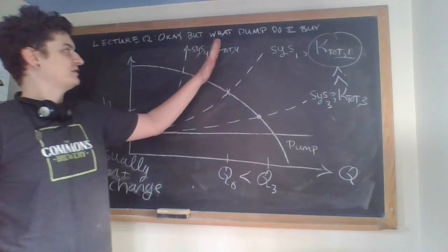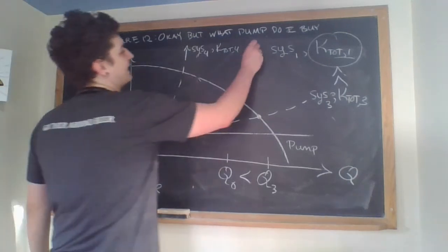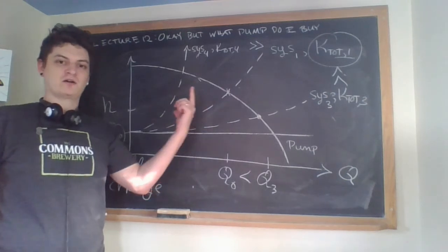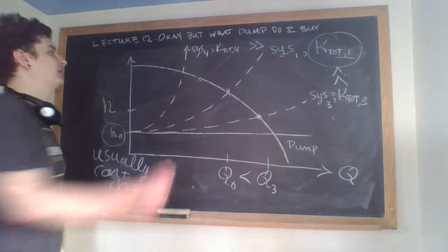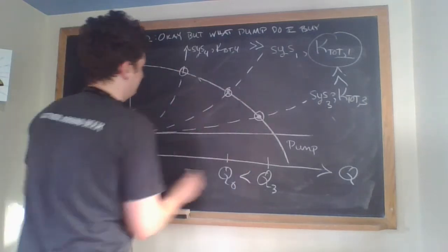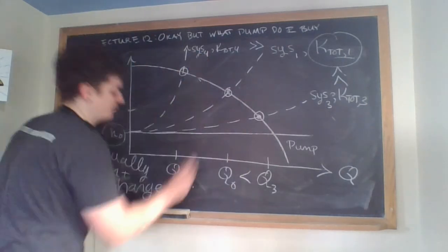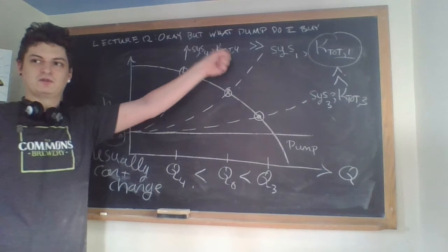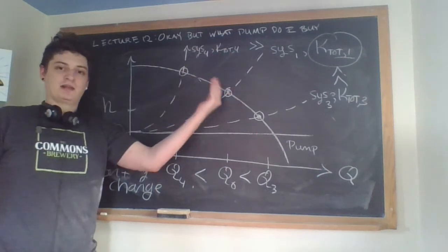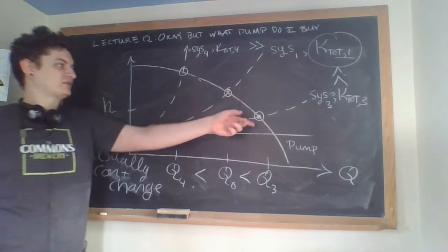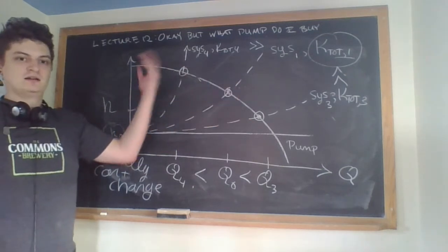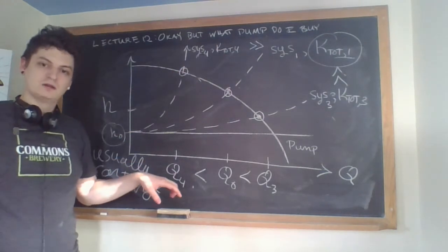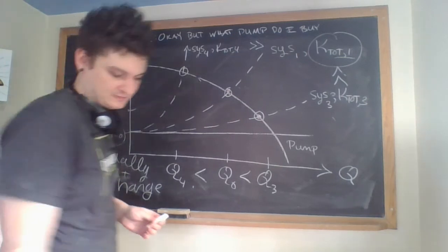Likewise, I could do this term, right? This one right here is actually a much, much steeper polynomial curve this time around. And what did that do? That made me go here, and this will be 4. So really, really big flow resistance terms right there. Draw this curve, make it more curvy, make it curl upward, and that's drawing this operating point closer in. So increasing the resistance here draws your operating point flow lower. And those are important to look at.